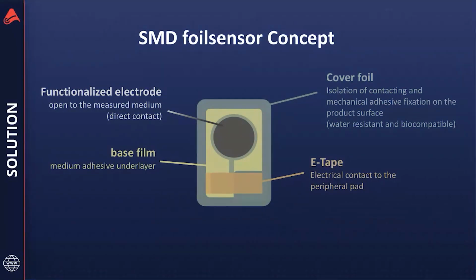We have the cover foil, in green a little bit, which is the isolation of the contacting and the mechanical adhesion fixation on the product surface. And this is a water-resistant adhesive, of course, and also biocompatible, because one of our target branches is medical and biotechnology. And there is a hole in the middle because our electrodes, if you talk about biosensors or ion-selective electrodes, need to be in direct contact with the analyte fluid. And so we have an open hole there. And this is a functionalized electrode. And this is one of our USPs, to bring on this electrode surface a special coating which creates the sensitivity to the target parameter.